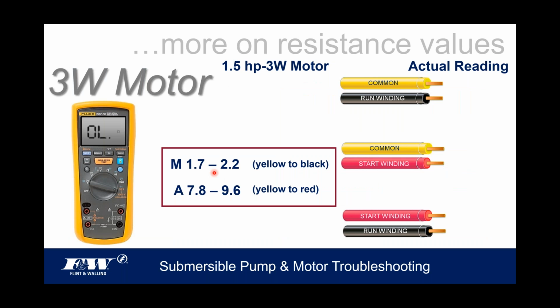This is the last of the tests we're going to perform here, and this is also probably one of the rarest occurrences. But if you look, I just put my probes on my yellow and black. I've got that 8 ohms up there. That's higher. That's no good. I'm going to drop down to the next. I'm going to do the common and start winding, and I put my ohm meter on there. That's lower, right? So now I'm coming in higher and coming in lower. That's no good. And again, by this point, you don't need to do anything with that start and run winding. The problem's already showed itself.